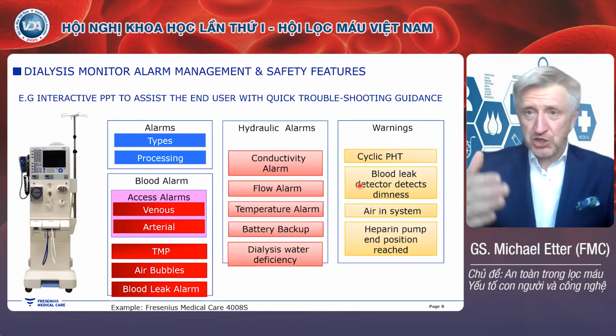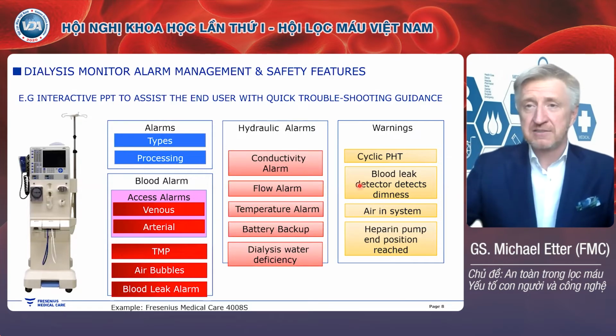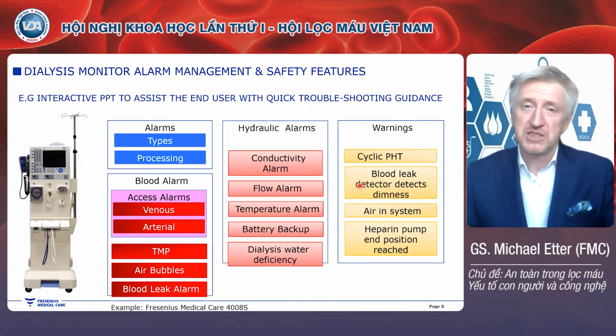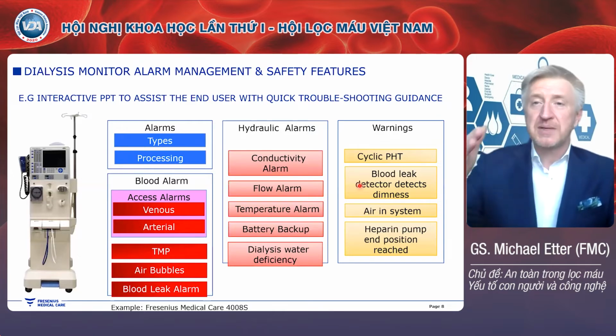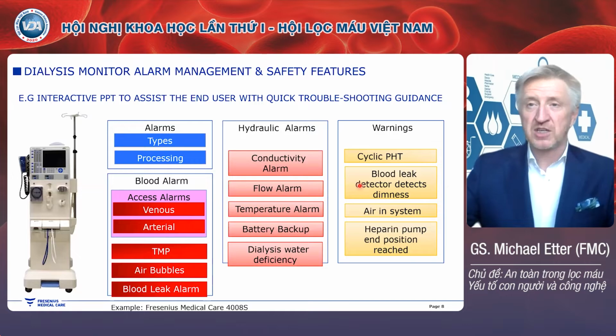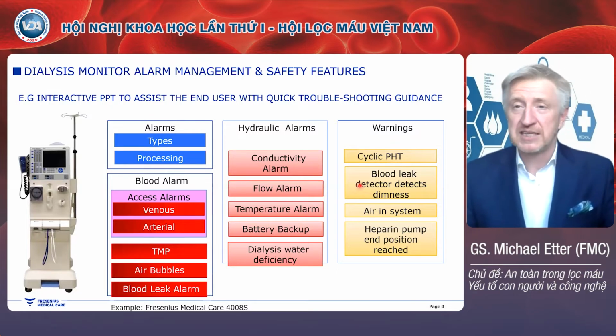And in the future, some of the next features that will come with dialysis machines will use some of these elements to actually automatically stabilize the patient on dialysis. For example, the conductivity alarm: the conductivity system controls the electrolyte concentration in your dialysate and also in the patient's serum. So there are interesting things coming up looking at this, but these alarms are on the side of the dialysate.